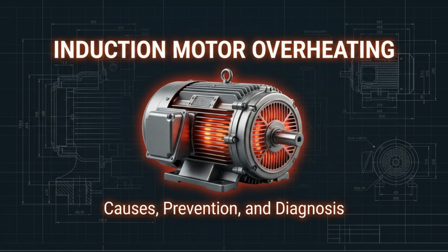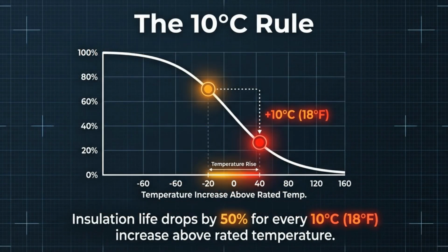Welcome to this video on induction motor overheating, covering its causes, prevention, and diagnosis. The 10 degrees Celsius rule shows how critical temperature is. For every 10 degrees Celsius increase above the rated temperature, the motor's insulation life drops by 50%.